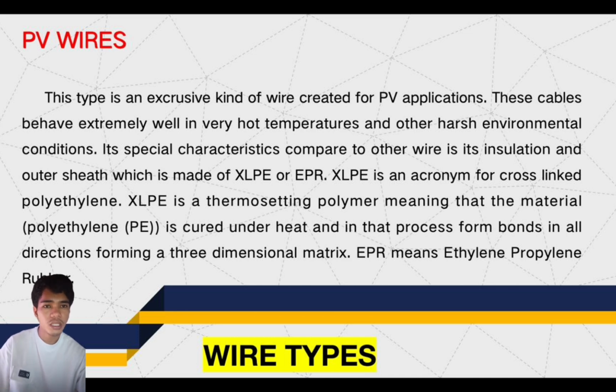PV wires. This type is an exclusive kind of wire created for PV application. This cable behaves extremely well in very hot temperatures and harsh environmental conditions. Its special characteristic compared to other wire is its insulation and outer sheath, which are made of XLPE or EPR. XLPE is the acronym for cross-linked polyethylene. It is a thermosetting polymer, meaning that the material is cured under heat and the molecules bond in all directions, forming a three-dimensional matrix.